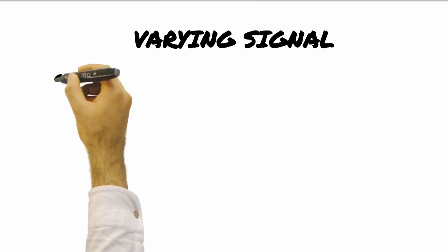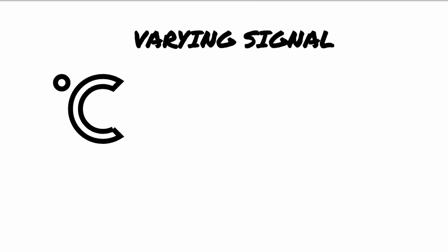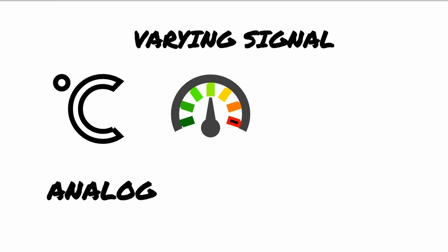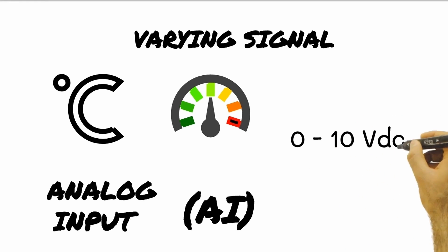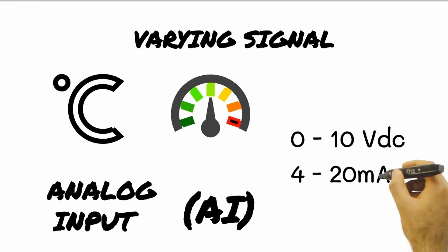A varying signal such as temperature, humidity, or pressure is called analog signal. In DDC terms, it is called analog input or AI. The most common type of analog input from instruments are 0 to 10 volts DC and 4 to 20 mA.